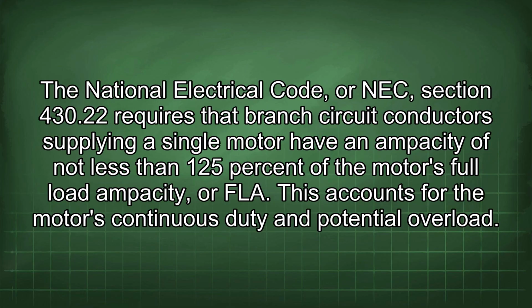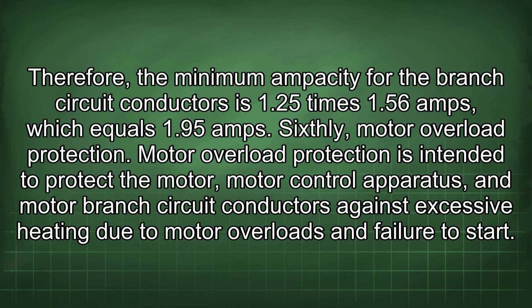Fifthly, motor branch circuit sizing. NEC Section 430.22 requires that branch circuit conductors supplying a single motor have an ampacity of not less than 125% of the motor's full load ampacity. This accounts for the motor's continuous duty and potential overload. Therefore, the minimum ampacity for the branch circuit conductors is 1.25 times 1.56 amps, which equals 1.95 amps.